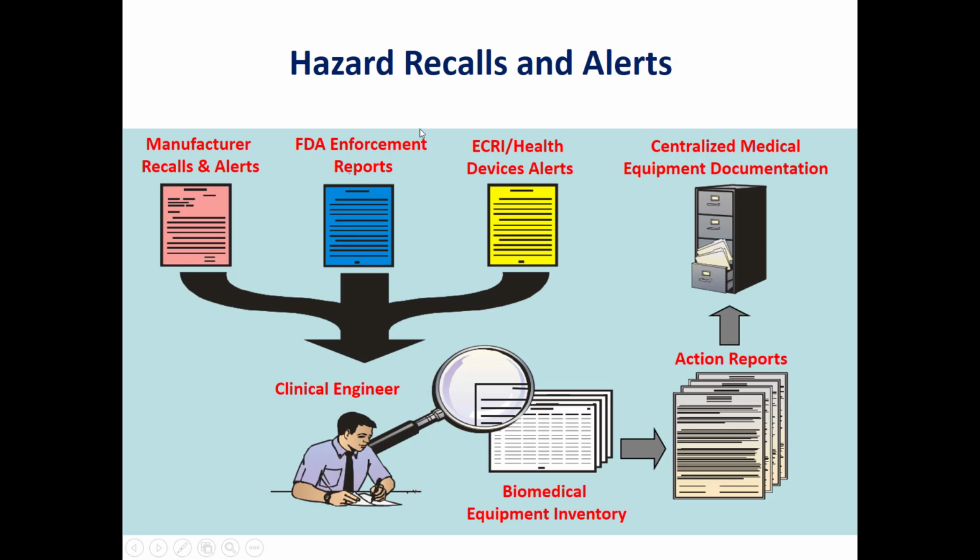Here we see a diagram which clarifies the above mentioned policy and procedure. We have recalls and alerts from the manufacturer. We have also FDA enforcement reports, for example, if we are in USA or outside USA. We have also a useful source for recalls and alerts from the ECRI.